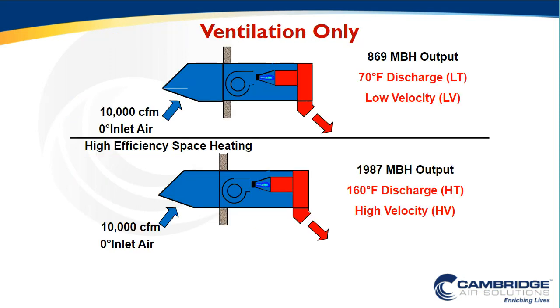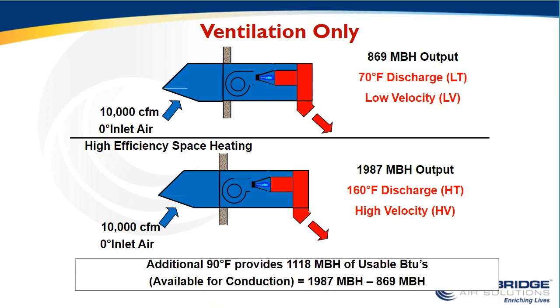And in essence, that is what takes our standard off-the-shelf kitchen ventilation makeup air system into a high-performing, low-energy HTHV system, such that by dialing up the discharge to the maximum safety standard allowable, we can then create more heat and more energy to counteract any skin losses without adding any ventilation air, without adding any recirculation air, and without adding any additional systems, such that now we have a fully functioning high-temperature heating and ventilation system. And what this simple principle allows us to do is that the HTHV system gives us an additional 90 degrees of temp rise, or 1.1 million BTUs of usable heat to heat any conductive losses.